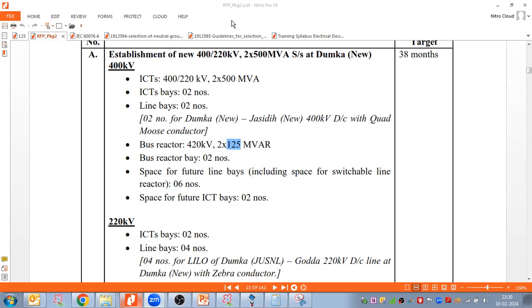So, to my knowledge, it is no. There is no controller; we have to close the reactor by panel, meaning through a circuit breaker we have to close the circuit breaker, and that reactor will be energized. There is a controlling switching device for the closing pulse, but the command has to be executed manually for that pulse location. There is a device like AVR for the OLTC, but there is no such device for the reactor. So we don't have an AVR or OLTC for the reactor.